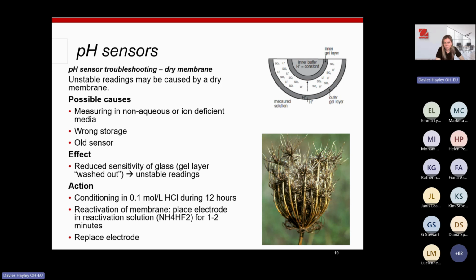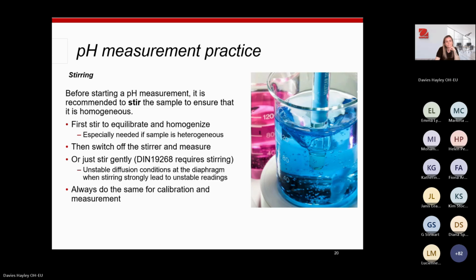If that doesn't work, if there is a really mild hydrofluoric activation solution that you have access to, you can pop it in that solution for 1 to 2 minutes. 1 to 2 minutes only, and then you need to take it out. You need to then rinse it with distilled water, and then you need to recalibrate. If neither of those things work, it may be that the electrode just needs to be replaced.